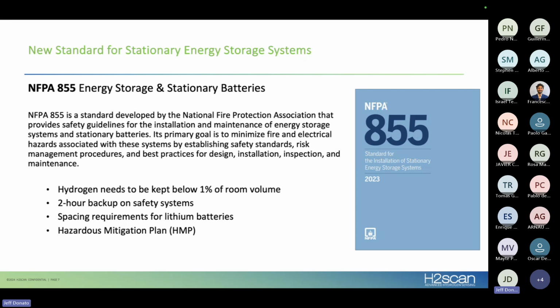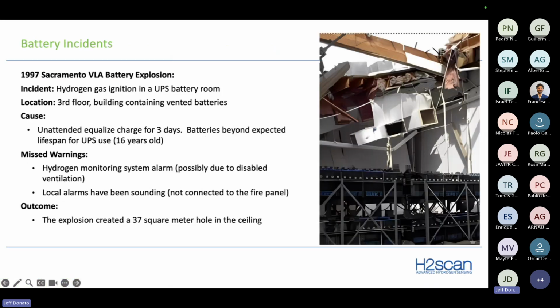And just like the photo we saw in the prior slide, where we had this explosion in the ceiling, the reason why this explosion happened was that the alarm was audible, but it wasn't transmitting to somebody to be able to take action. The fire department actually showed up to evaluate this site when alarms were going off, and they didn't see any alarms in the fire panel. So they left the site, and they assumed that it was something else in the building creating the noise. So in this case, it was a missed opportunity to mitigate this hazard.